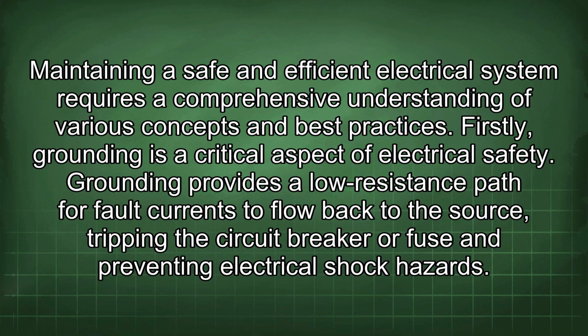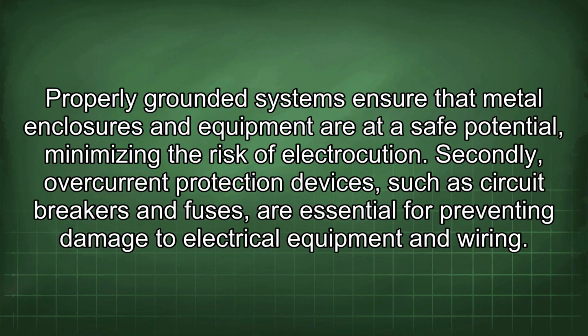Grounding provides a low-resistance path for fault currents to flow back to the source, tripping the circuit breaker or fuse and preventing electrical shock hazards. Properly grounded systems ensure that metal enclosures and equipment are at a safe potential, minimizing the risk of electrocution.